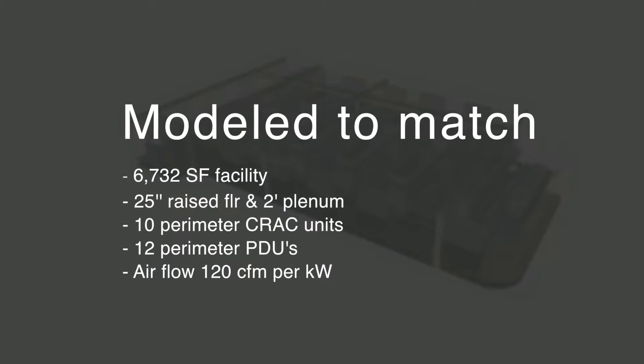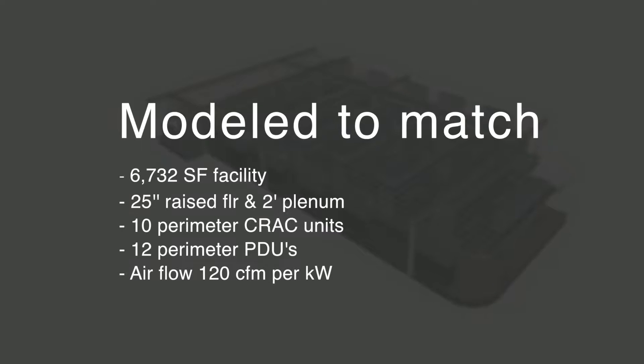We modeled our 6,700 square foot facility with a 25-inch raised floor and 2 feet of ceiling plenum, 10 perimeter CRAC units, and 12 perimeter PDUs. Airflow through each cabinet is approximated at 120 CFM per kilowatt of heat load.